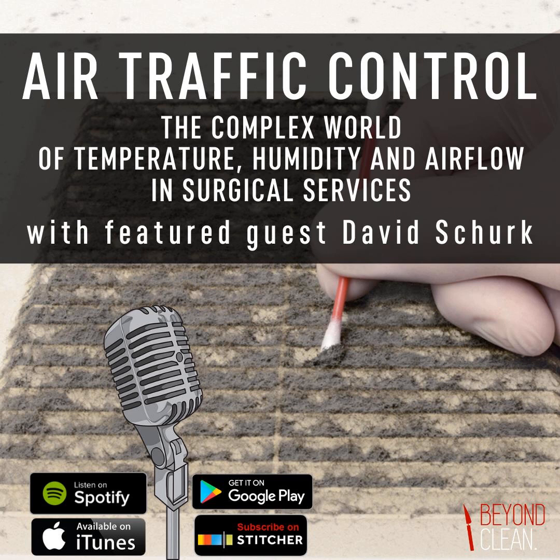I have seen many hospital facilities where the HVAC systems are basically breeding grounds for biological contaminant, biological growth, mold, mildew, fungus, things of that nature. And what I have seen is the occurrence of those issues, particularly inside air conditioning units, particularly in the cooling coil cabinet areas where you've got moisture from condensate, you've got a dark, cold environment. The coils can load up with dirt if the filters aren't clean, and of course that creates the perfect breeding ground for mold.